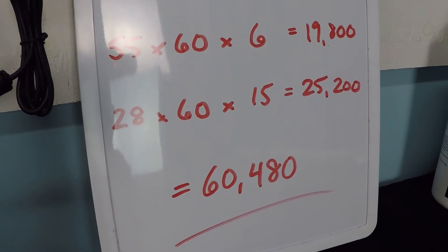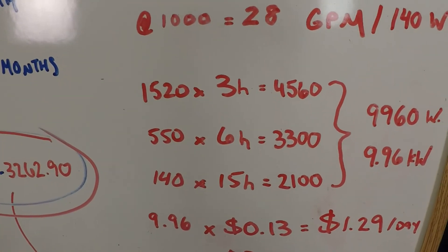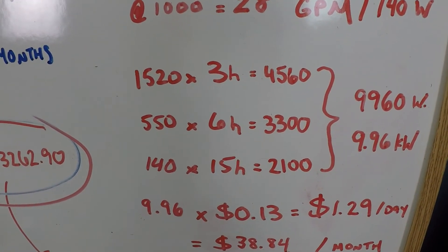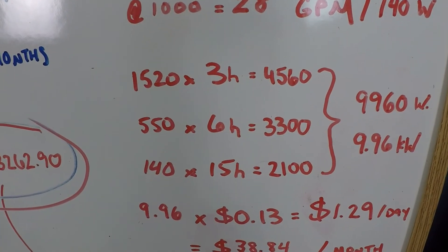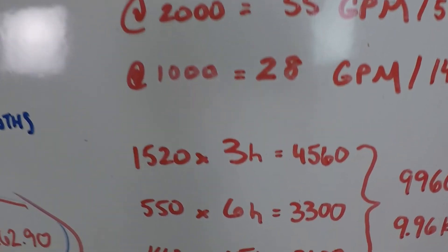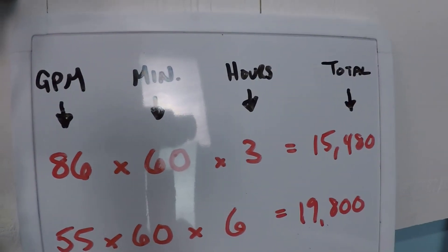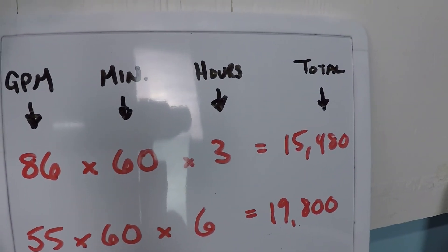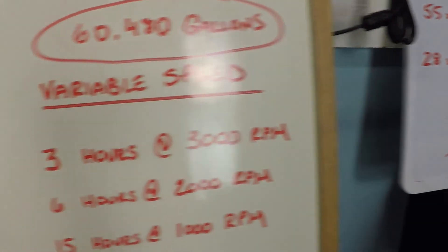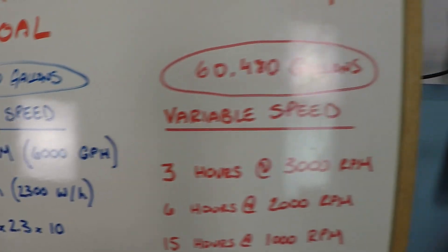What is specifically interesting about that, if you look at the power consumption during these periods of time, the 15 hours of operation at low speed used less than half of the power of the three hours at higher speed. That's really interesting because you paid more in power to get 15,000 gallons than you did to get the 25,000 gallons. And that's why, cumulatively, the single speed just can't compete. It cannot compete.